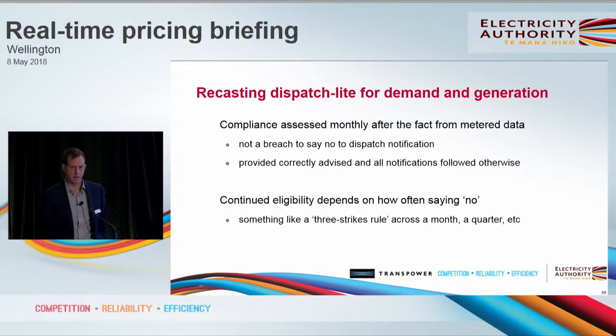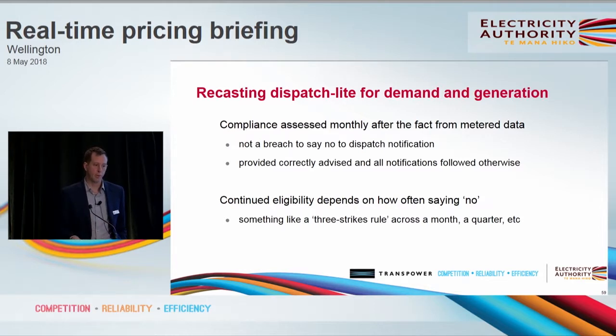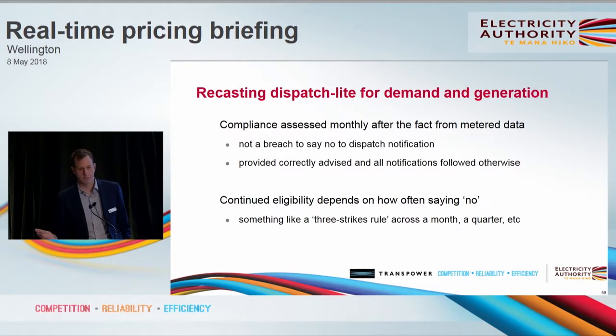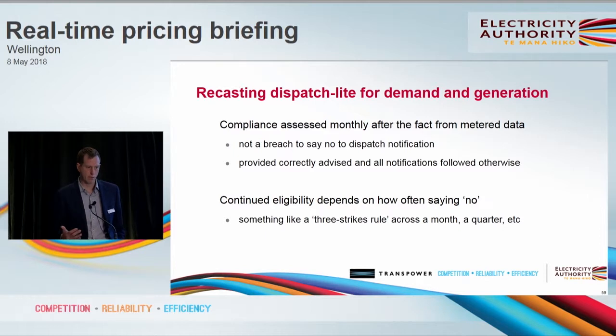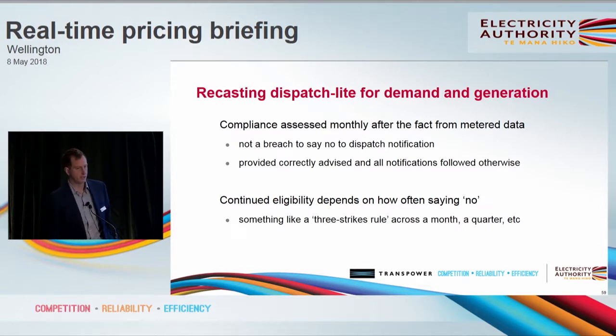Assuming we go with that megawatt limit version, compliance would be assessed monthly, after the fact, from metered data — because without real-time telemetry there's no ability for the system operator to see if you're on or off dispatch at any given point in time. It would not be a breach of the code to say no to a dispatch notification. As we've said, if you do it too often you might get kicked out — maybe for a month, maybe permanently. But that's only if you follow the correct process and advise by rebidding or re-offering, declaring that new form of bona fide, and follow all notifications you didn't say no to. If you don't follow them, then you're in breach of the code in the same sense as if you don't follow an instruction.